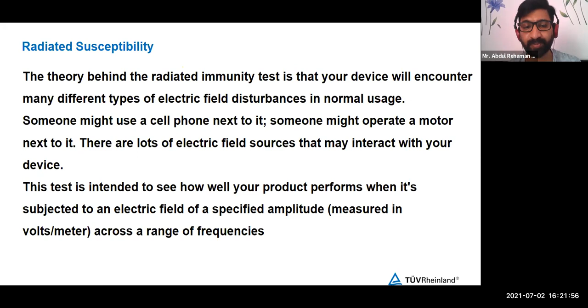Basically what we do over here is, when I say we inject the noise, there is a carrier frequency which will be superimposed with an amplitude modulated signal. This amplitude modulated signal gets injected to the product. Here, the product, the EUT, is kept on the table for tabletop equipment, where we'll have an antenna which radiates the noise and gets injected onto this product so that the performance can be monitored.